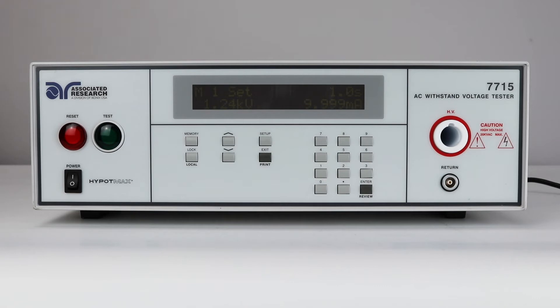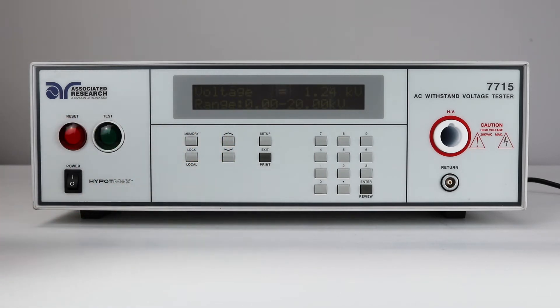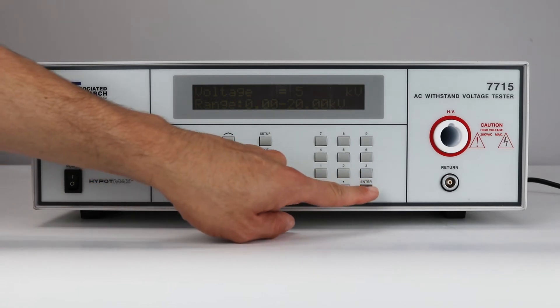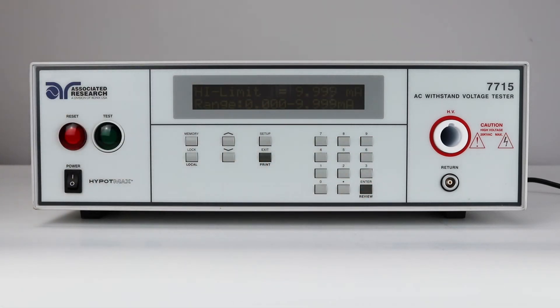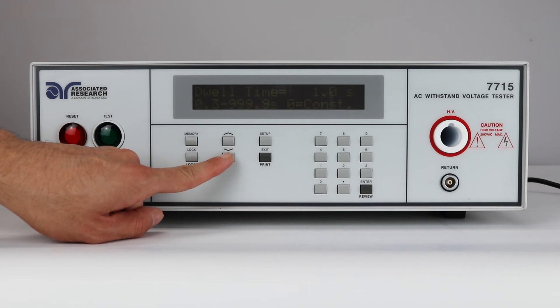Next, we will need to set up the parameters for the AC Hi-Pot test. To edit the parameters, simply press the up and down arrow key to navigate through the test parameters. If entering a numeric value, such as voltage, use the numeric keypad to input a value. To toggle between parameter selections for frequency, dwell unit, arc detect, and connect, press the enter key to scroll between the values.